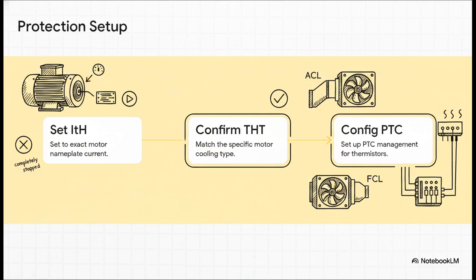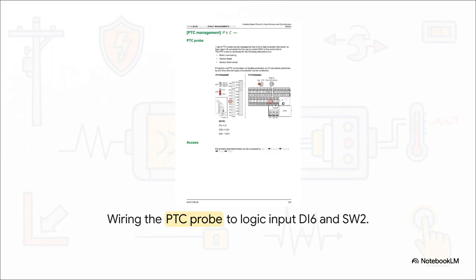Okay, so once you're in that FLT menu, dial in your ITH to match your motor nameplate. Then you want to check THT, which is the motor thermal monitoring mode. Out of the box, it defaults to ACL for standard self-cooled motors. But if you've got a separate forced cooling fan strapped to your motor, you'll definitely want to change this to FCL.